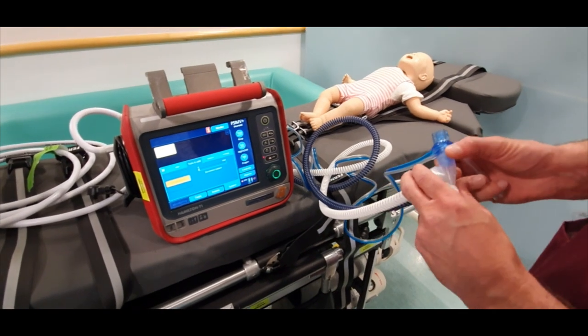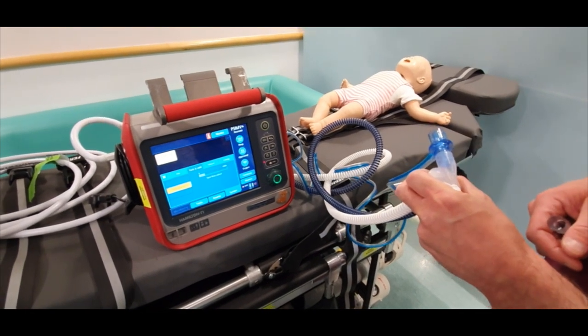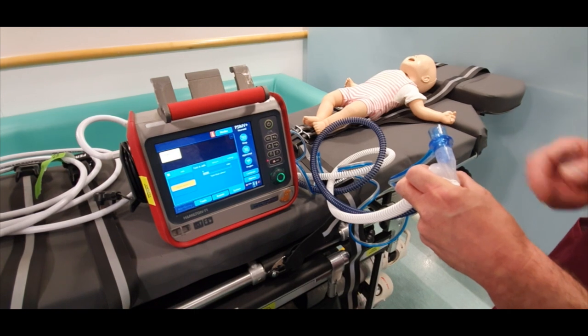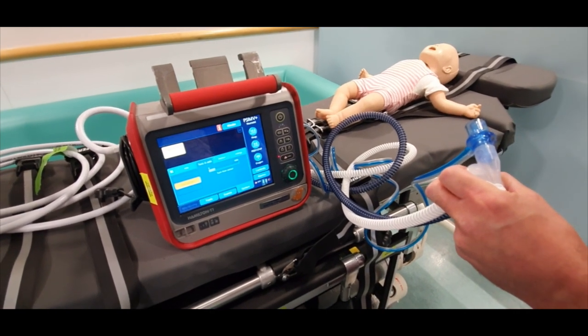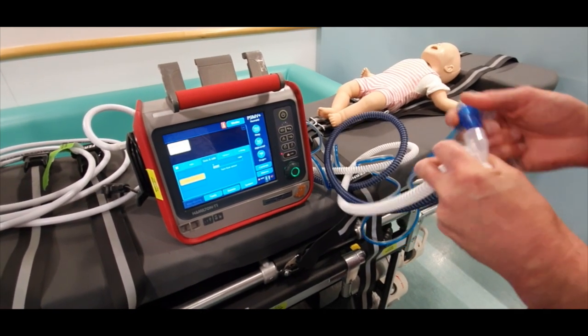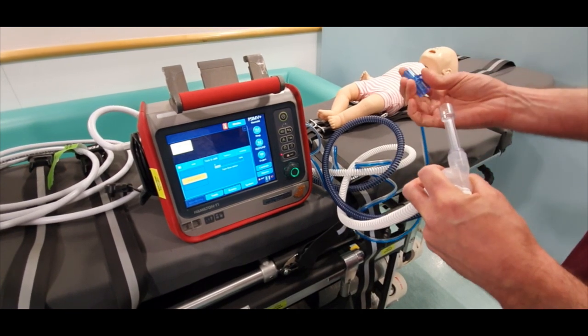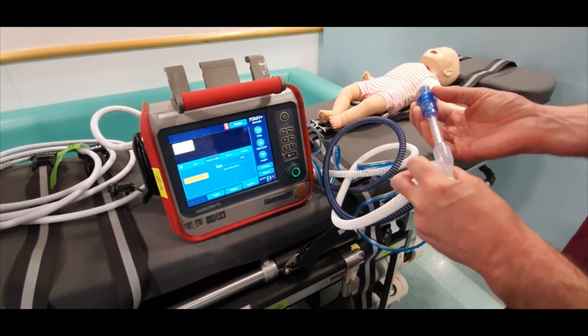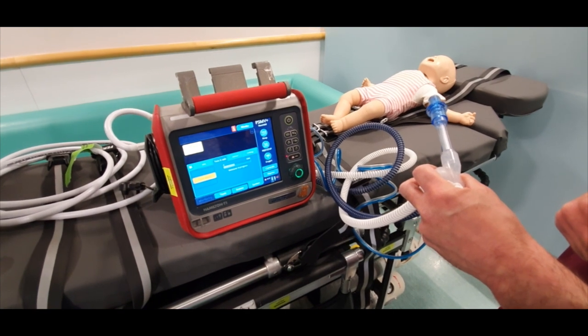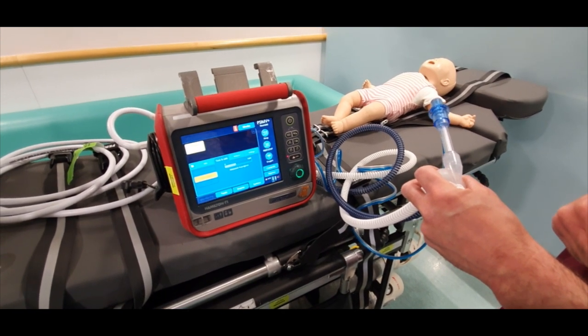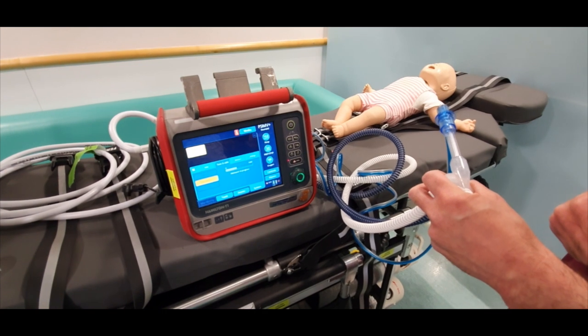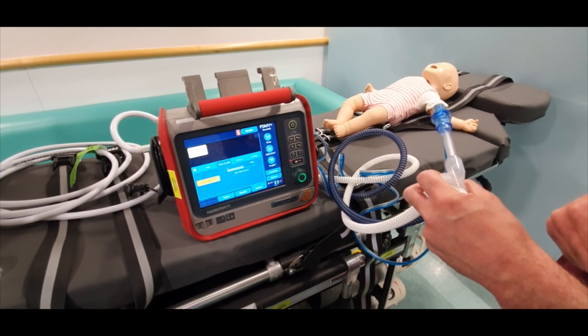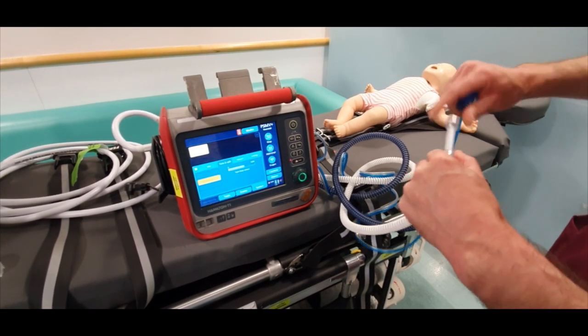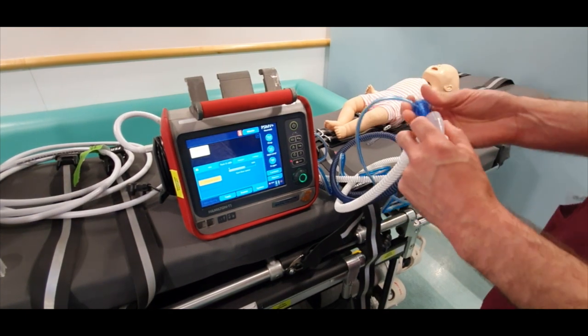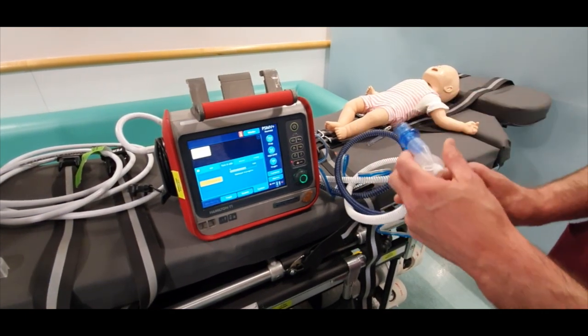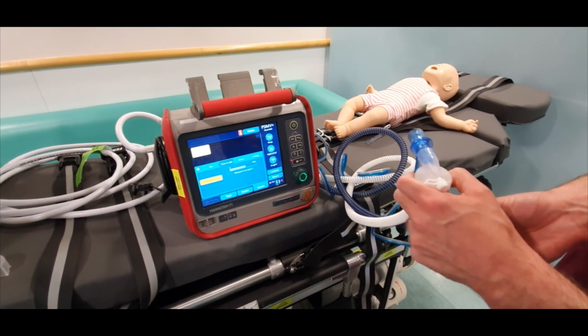Next, the flow sensors are calibrated. The machine requires the sensor to be disconnected and turned back to front using the included adapter as part of the test, as Mike nicely shows. This takes a bit of time, so has been sped up. The flow sensor is swapped back to its usual position to complete the test.